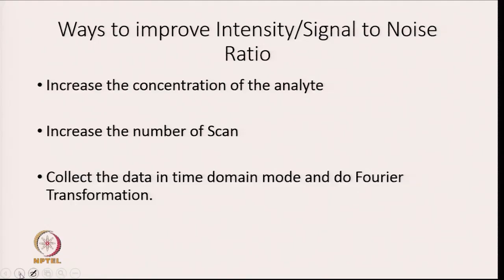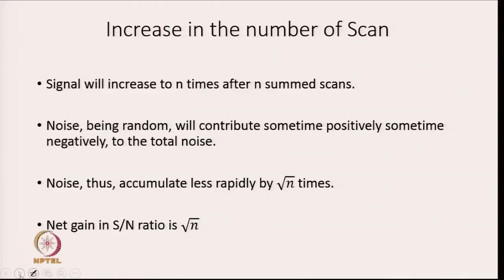As discussed earlier, NMR is a low sensitive technique, so we need to find methods to increase the signal-to-noise ratio. One way is to increase the concentration of the analyte — though this is not always possible. The second way is to increase the number of scans, collect data in time domain mode, and do Fourier transformation. If we take N scans, the signal will increase N times, but noise being random accumulates only by root N times, so the signal-to-noise ratio gain is root N times.